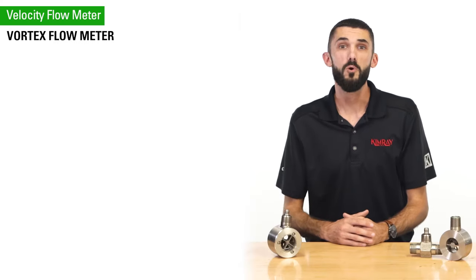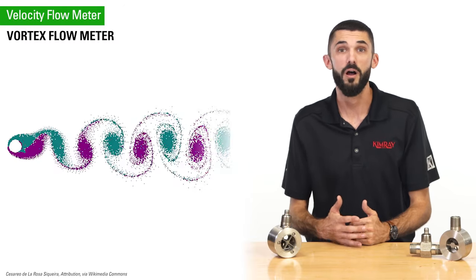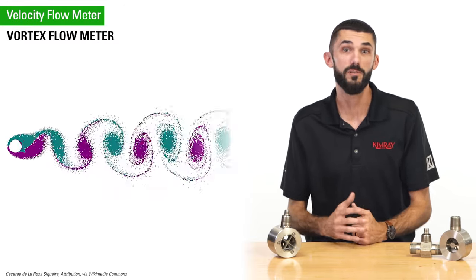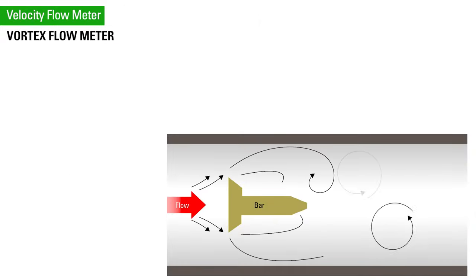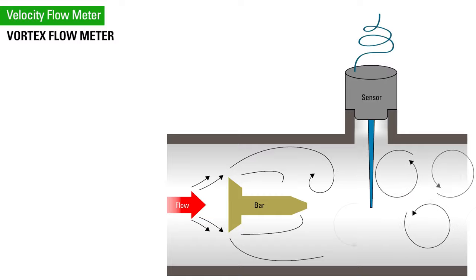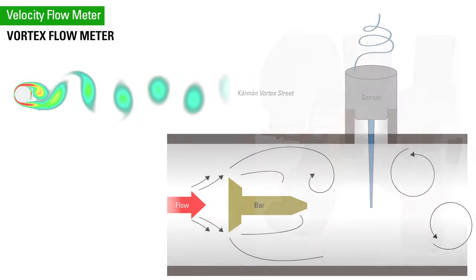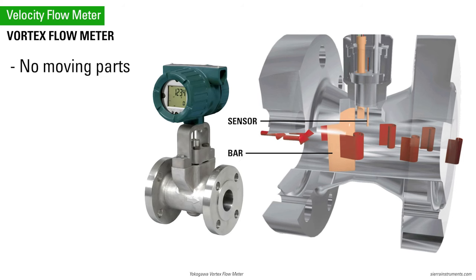Vortex flow meters operate under the vortex shedding principle, where an oscillating vortex occurs when a fluid flowing past a bar positioned in the flow path generates a frequency that can be read by the meter. Because there are no moving parts, it is ideal for applications where low maintenance costs are important.